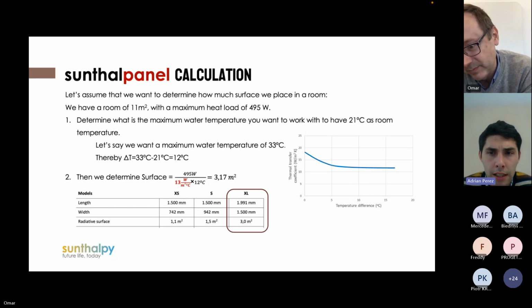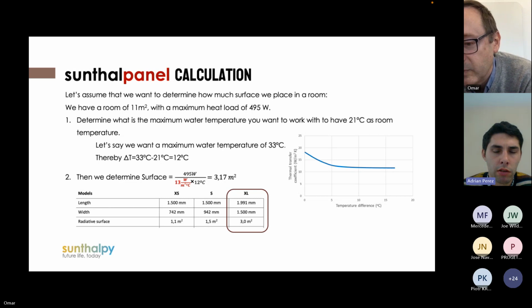This is an installation question: how are the panels balanced compared to using a lock shield valve on a radiator? Is it not an issue if these connections are no longer accessible — for example, needing to reduce flow to panels closest to the heat source? How does this work?